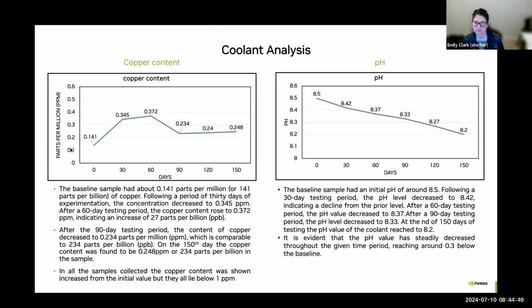Okay. And did you all run a control test? You're running this loop at a higher velocity than the recommendation of 1.5 meters per second. Did you run the same test in the same period of time on a separate loop with the velocity at 1.5 meters per second so that you could compare these two?